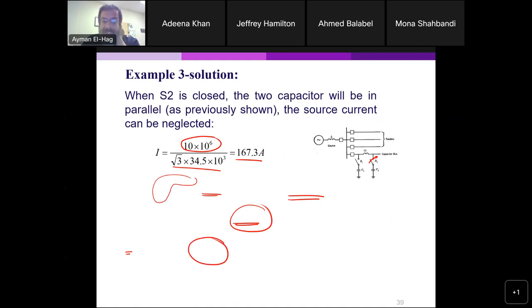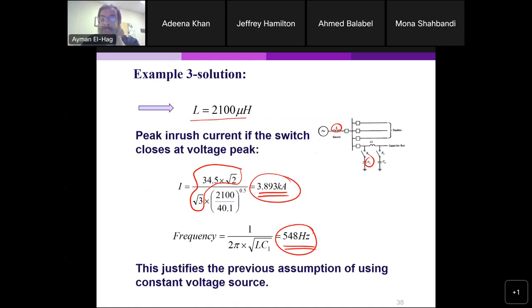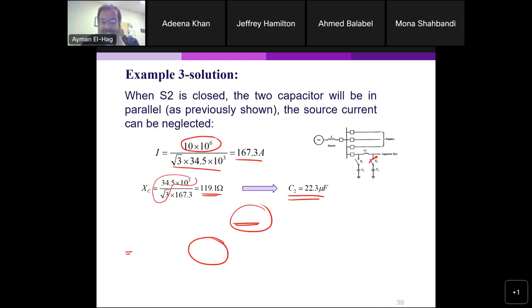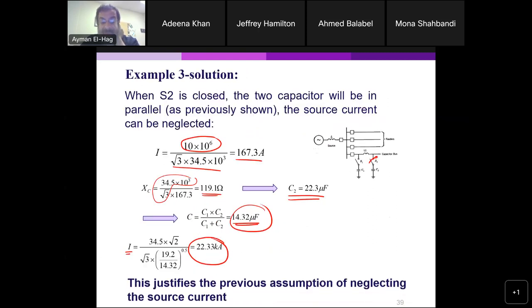22.33 kiloamps. So let's see the current coming from the source. It was 3.89 kiloamps, much less than this current. So that basically justifies the assumption that we will ignore the current coming from the source. Why? Now it is almost 1/10. So the basic idea here is to make an assumption which makes the calculation very, very easy, but at the same time does not jeopardize your accuracy. And the frequency here now comes in kilohertz. So the second time you switch a capacitor, you will have higher current and also much higher frequency.